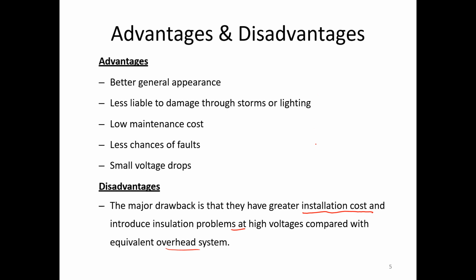When we compare at the same voltage level, for example transmitting 132 kV in an overhead system versus 132 kV underground system, the main disadvantage is that at high voltage we need high insulation. In overhead lines, we can provide this insulation by maintaining an appropriate distance between two conductors because these are live conductors. But underground, we need more insulating material or more thickness of each insulation layer in the case of insulators and cables.